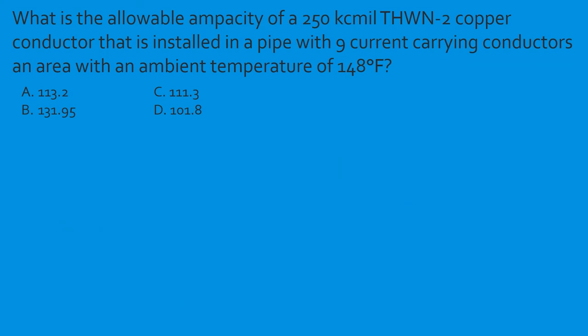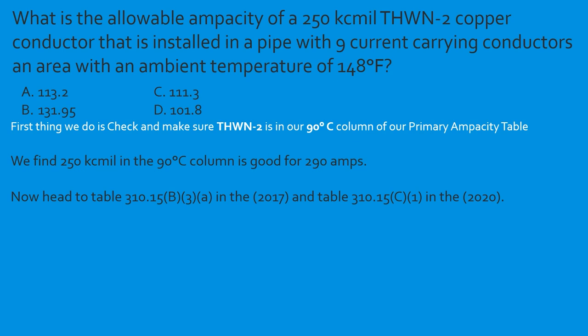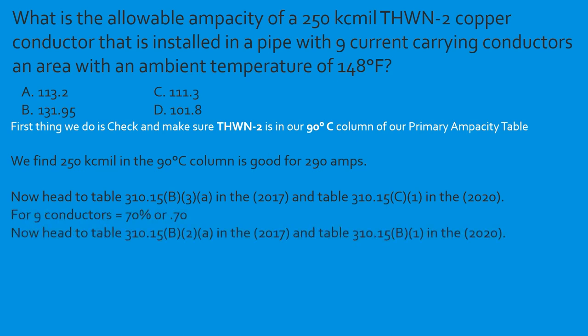Question: What is the allowable ampacity of a 250 kcmil THWN-2 copper conductor installed in a pipe with nine current-carrying conductors at an ambient temperature of 148°F? Confirm insulation is in the 90°C column. 250 kcmil is good for 290 amps in the 90°C column. Nine conductors — bundling adjustment factor is 0.70. Temperature at 148°F — correction factor is 0.65. So: 290 × 0.70 × 0.65 = 131.95 amps. Select B.